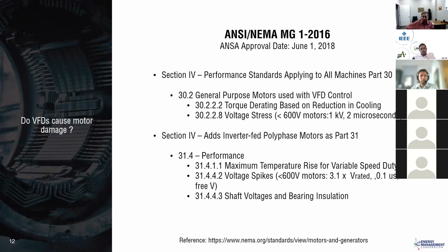Again, under the 600 volt and less motors, they're suggesting that the motor is rated at 3.1 times the rated voltage. So with a 460 volt motor, you're looking at 1400 and some volts. 480 volt motor, some look at it as a 480 volt motor, and that would be 1488. It's a little different than you might have heard in the past, because the standard started with a 1600 volt requirement. And so I've always thought, those motors had to be able to withstand a 1600 volt peak. And of course, the rise time is also able to come down. You have to have greater than a 0.1 microsecond rise time and be free of partial discharge. And if any of those terms are not familiar, we can talk about those more.